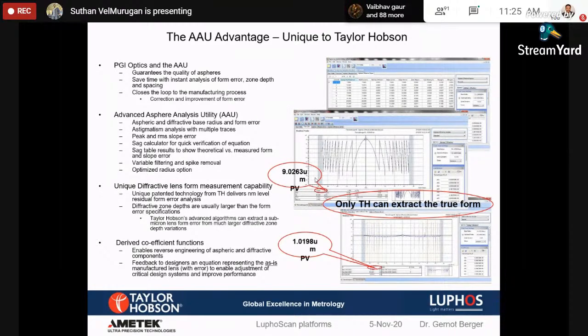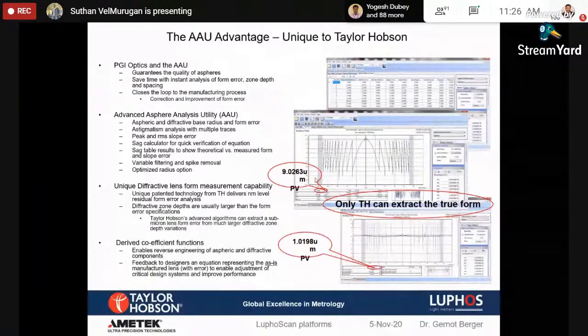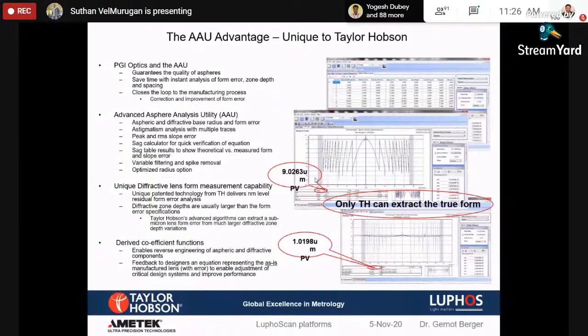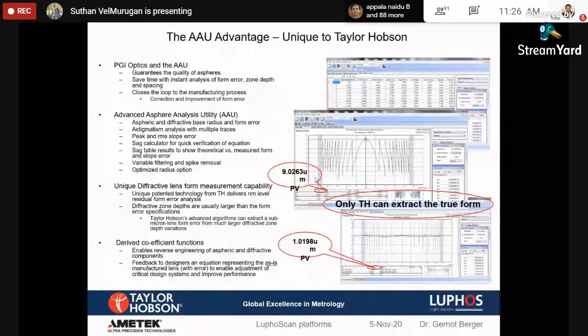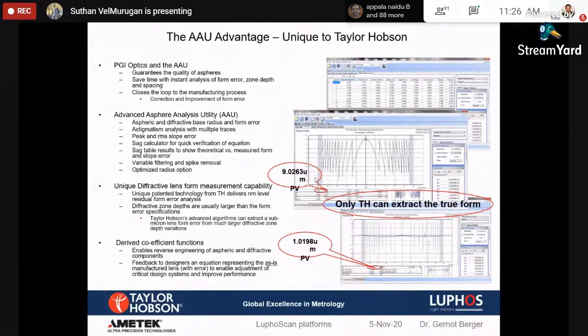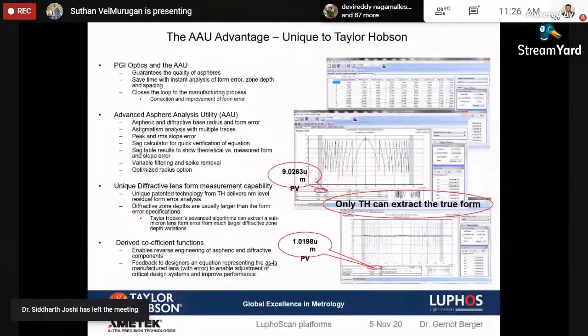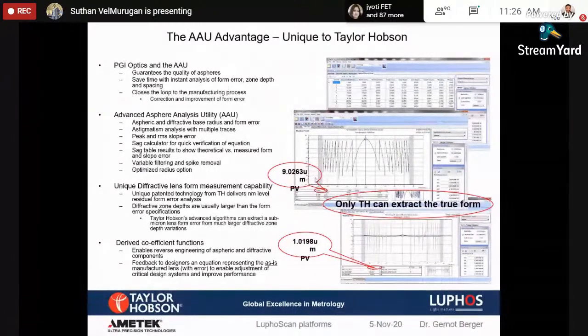In other words, we have a sample like an aspheric or diffractive form sample, but we don't have any design. We need to generate it from the aspheric coefficients. That is very much possible from the machine. Without knowing anything, you can just load the sample on the machine and trace it. The software can generate the aspheric equation for 10th order, 12th order, 20th order, and the base radius and the conic constant can all be generated. That is called reverse engineering. That is also very much possible with the PGI using the AAU software.